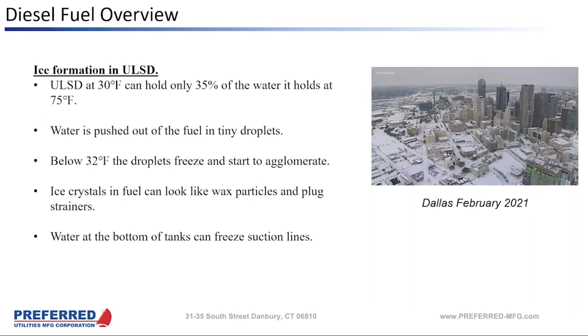And what he sent me looked just like a gelled fuel, but the ambient temperature had not been down to 18 degrees yet. We'd gotten below 32 at that point, but not all the way down. So I at first ruled out gelling of the fuel because it just hadn't gotten cold enough yet. But the picture he sent me looked just like gelled fuel. And it turns out it was ice crystals that had agglomerated together and clogged up a basket strainer. And it looked just like fuel that was gelled.